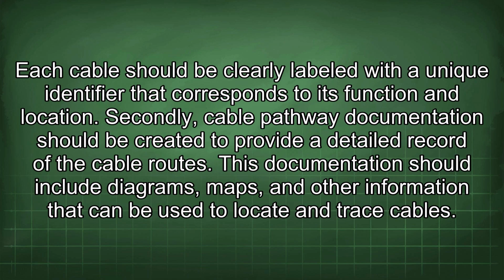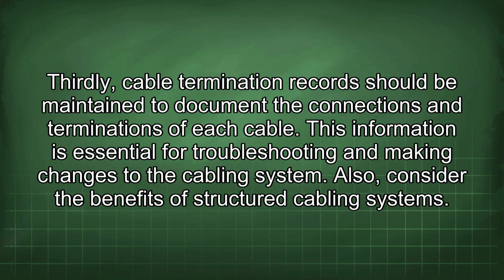Each cable should be clearly labeled with a unique identifier that corresponds to its function and location. Secondly, cable pathway documentation should be created to provide a detailed record of the cable routes. This documentation should include diagrams, maps, and other information that can be used to locate and trace cables. Thirdly, cable termination records should be maintained to document the connections and terminations of each cable. This information is essential for troubleshooting and making changes to the cabling system.